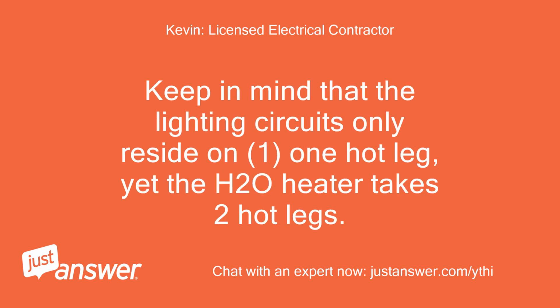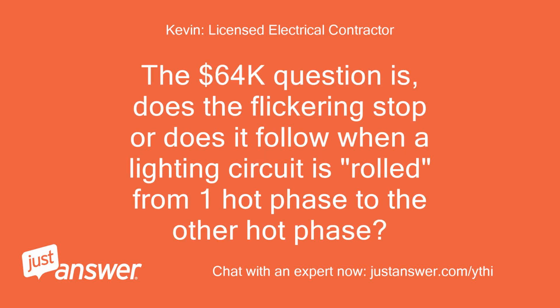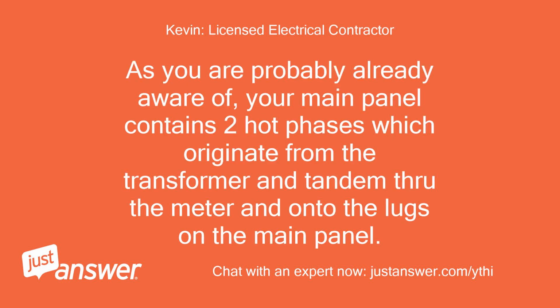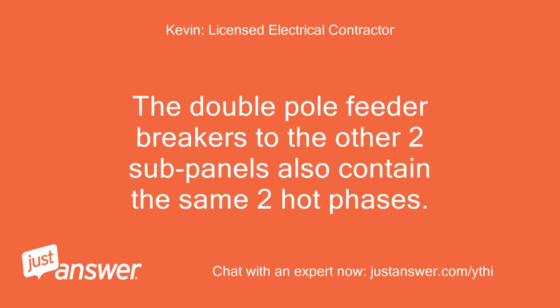Keep in mind that the lighting circuits only reside on one hot leg, yet the H2O heater takes 2 hot legs. The $64,000 question is, does the flickering stop or does it follow when a lighting circuit is rolled from one hot phase to the other hot phase? As you are probably already aware, your main panel contains 2 hot phases which originate from the transformer in tandem through the meter and onto the lugs on the main panel. The double pole feeder breakers to the other 2 sub-panels also contain the same 2 hot phases.